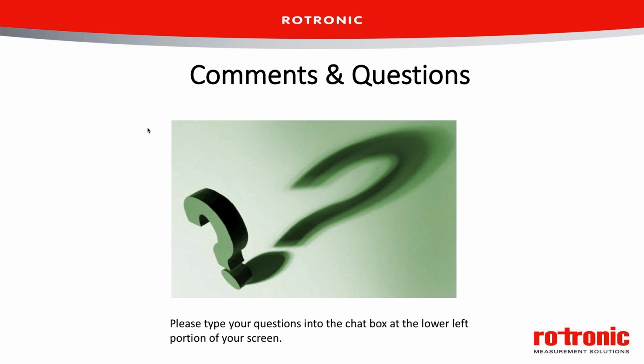Our next question is, for controlled temperature units, there is an empty chamber mapping and loaded mapping. How about warehouses? Okay, good question. With equipment mappings in a chamber, many times you do the mapping empty. That's because it's very hard on the control system. It's actually harder on the control system to control a space that has no product in it. When you put product in it, it creates mass, which helps the temperature mapping. So the worst case or the hardest case is actually empty.